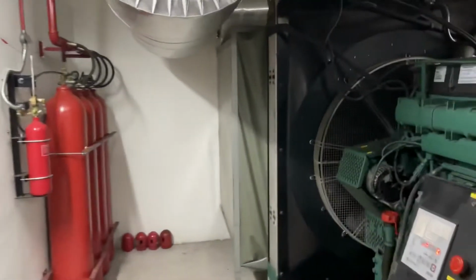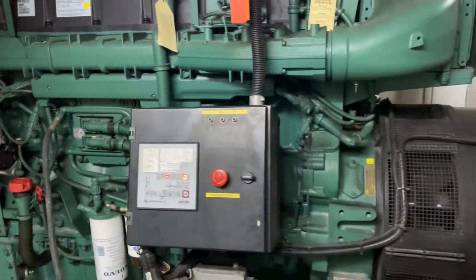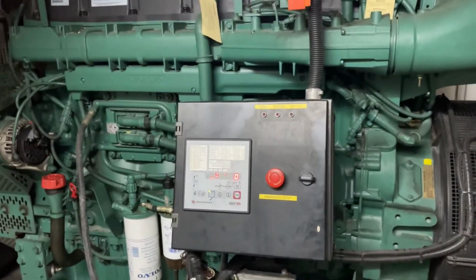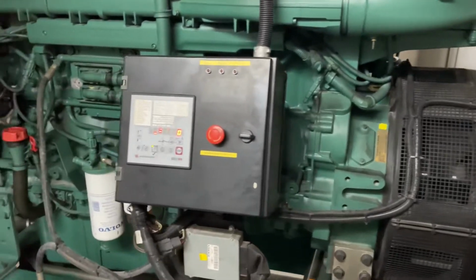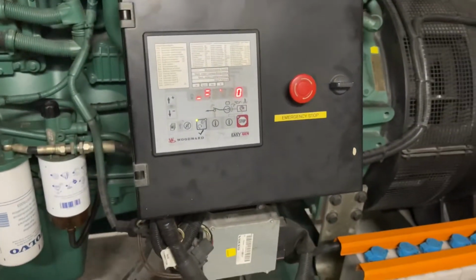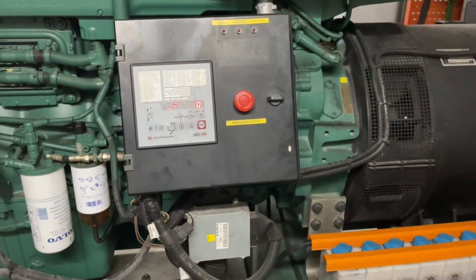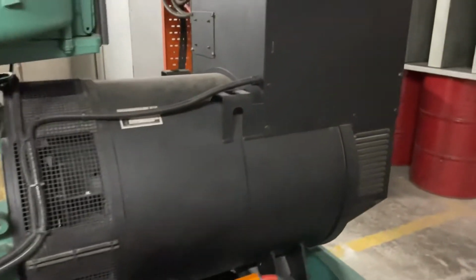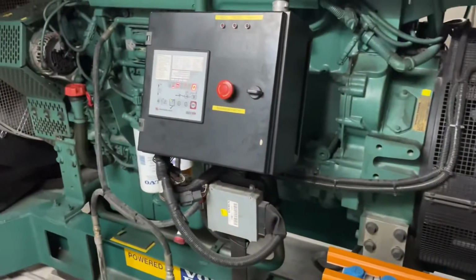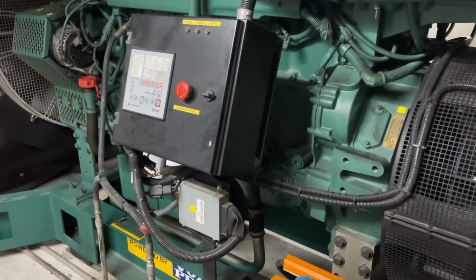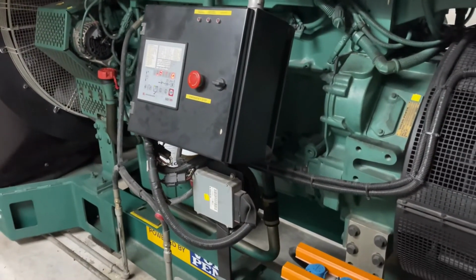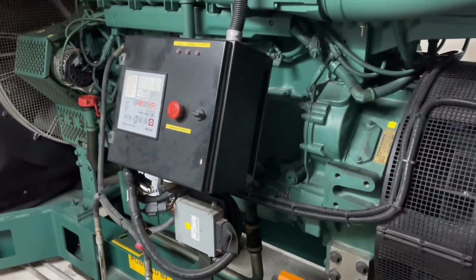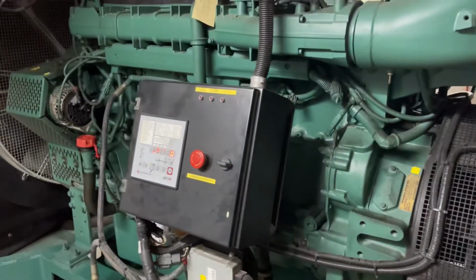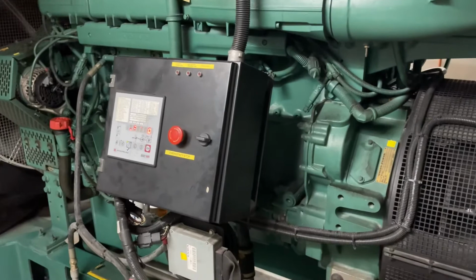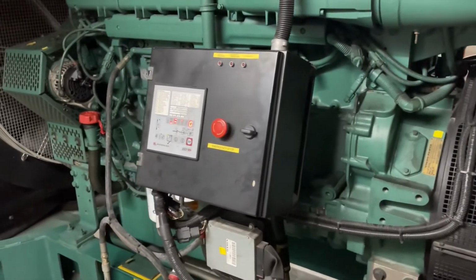Okay. Alright, here we have a genset. Okay. We're going to test run this genset under off-load condition. So today we are going to experience during the genset startup time how high the voltage will jump from idle speed to full speed. Okay, do take note, the voltage won't gradually go up. To certain genset, the voltage will shoot up until a certain level, then fall back down. Same as the frequency.